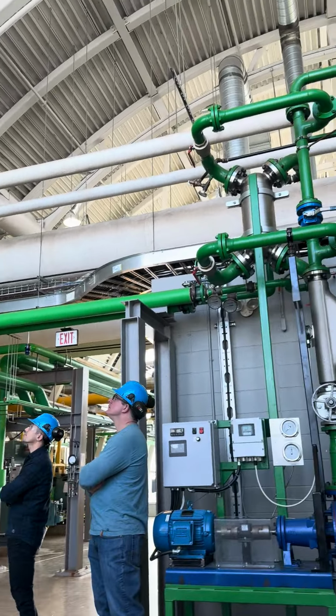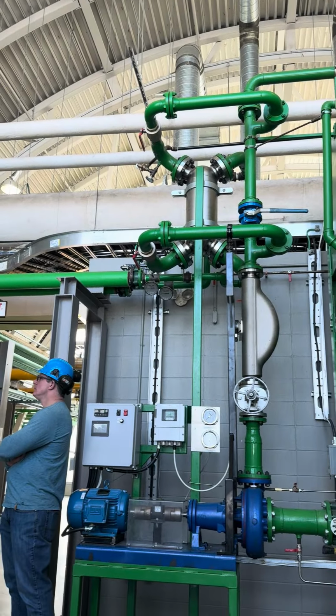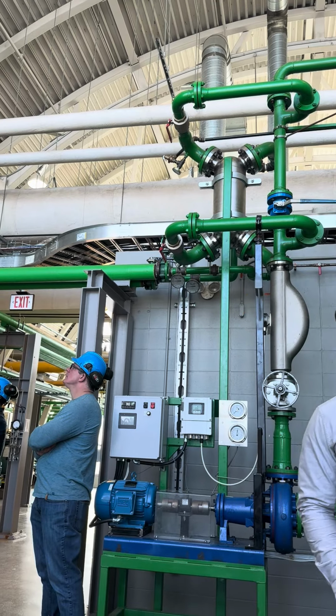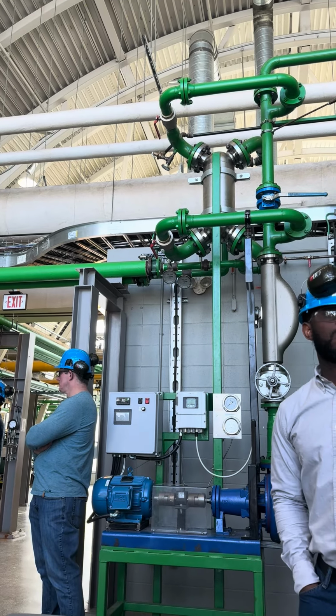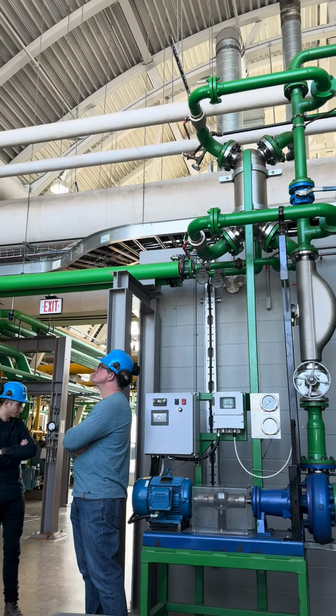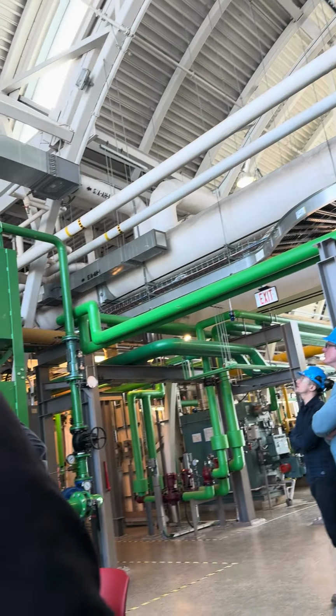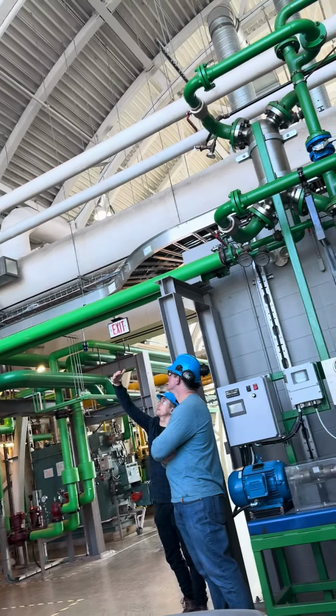But we have to have the return air too, right? Because we want to be positive pressure, our exhaust air is going to be a little bit less than our supply air. So you can see the ducts are a little bit smaller.